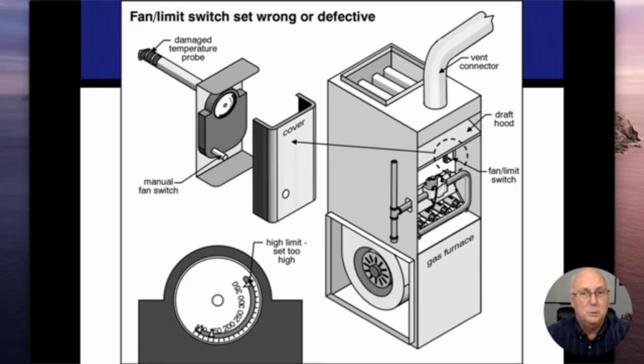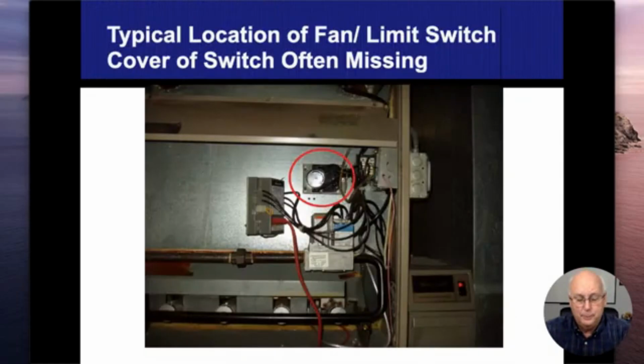And I've never run into this where this thing was set off that much. I do pull that cover off. I do check those numbers if I see an old furnace like this, just to make sure it's not there. But if somebody has this thing set up to 350 degrees just to keep that thing going, that's not a good thing. All right. They're really turning it into a gravity furnace, but the amount of heat that's there is not going to be a positive thing.